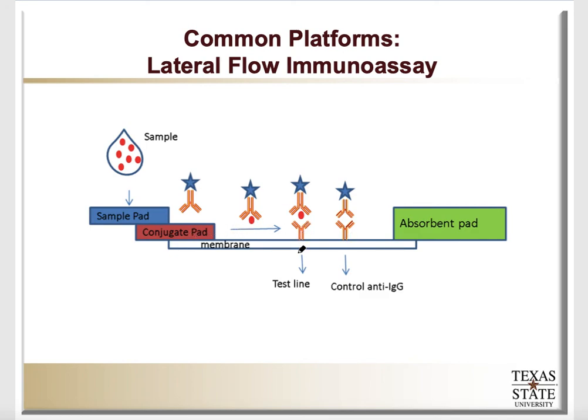Either the whole thing stopped here and didn't continue flowing, or the antibody all stayed here in the conjugate pad and something just went wrong. Now, if you don't get a line here, but you do get a line here, that means that the assay worked, but there was no analyte, nothing to capture, right? So everything basically just continued through.